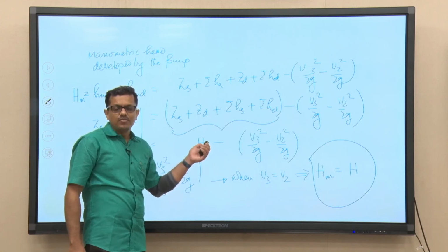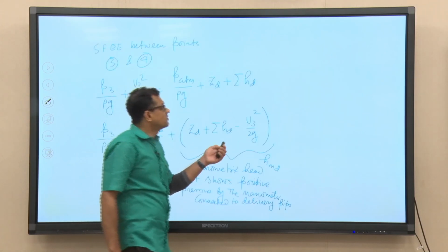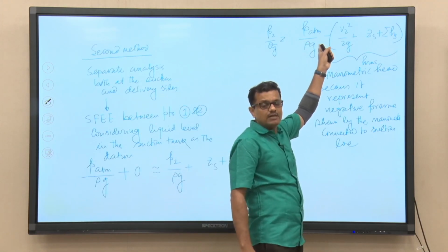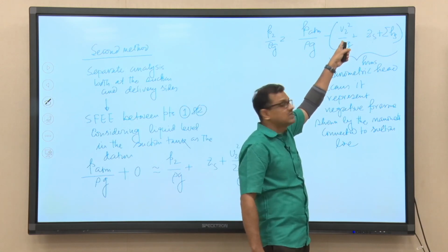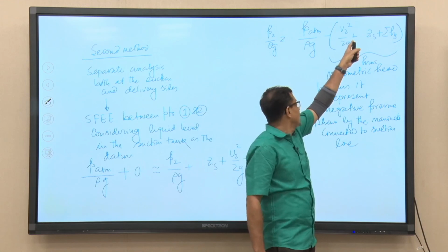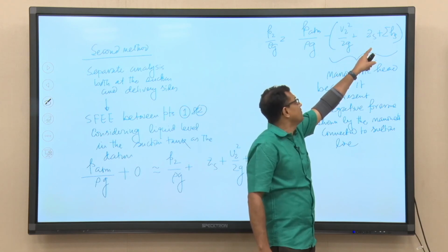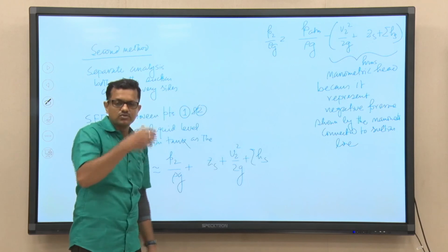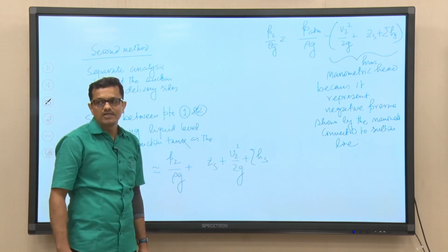The answer is, because of this analysis, at least we are in a position to understand that it is very important to know that the pressure at point 2 will be lesser than atmospheric pressure by this amount. So, by tuning parameters like the velocity at the suction line, the static height Zs, that is the height difference between point 1 and the suction valve, and also the frictional losses, by proper designing of the system we can control it so that cavitation will not occur.